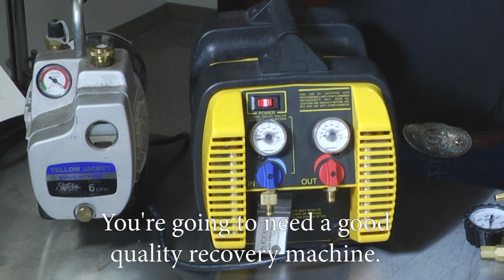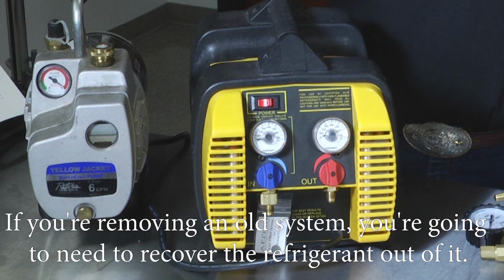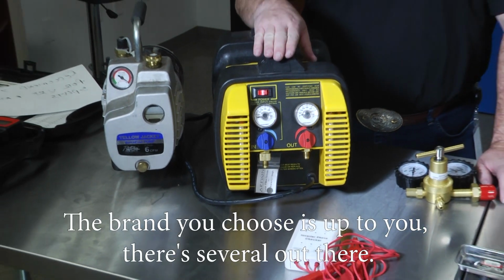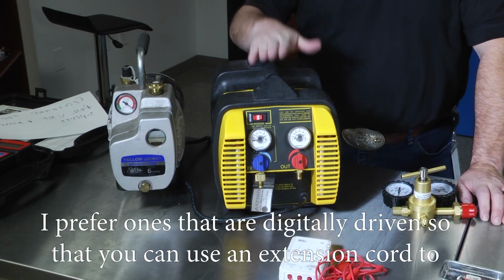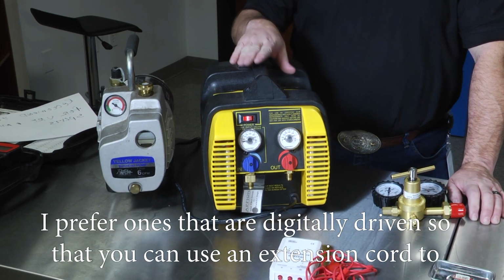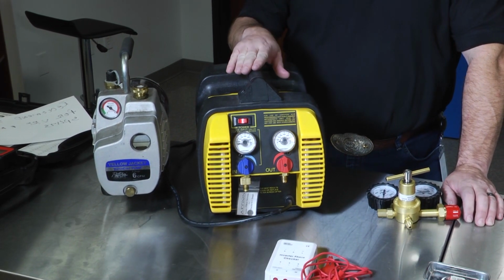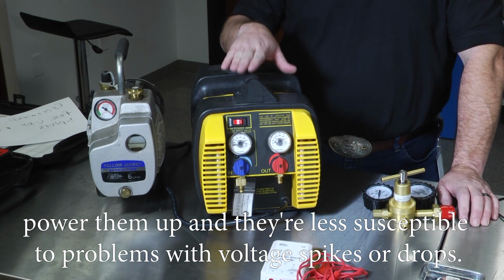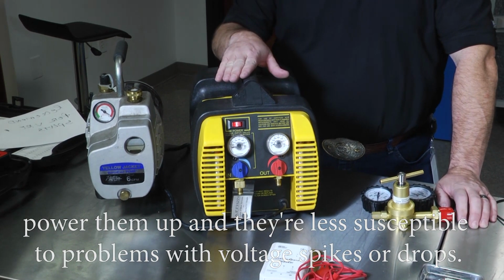You're going to need a good quality recovery machine. If you're removing an old system, you're going to need to recover the refrigerant out of it. The brand you choose is up to you. There's several out there. I prefer ones that are digitally driven so that you can use an extension cord to power them up, and they're less susceptible to problems with voltage spikes or drops.